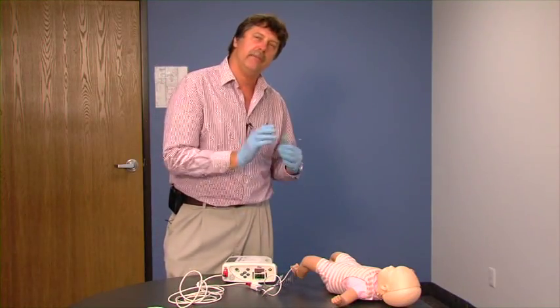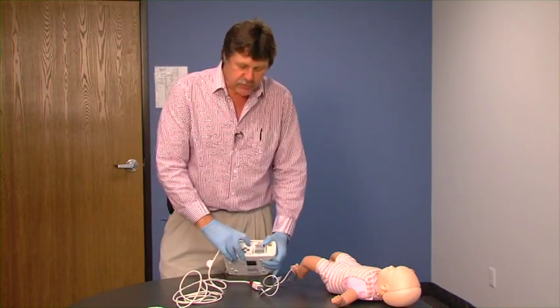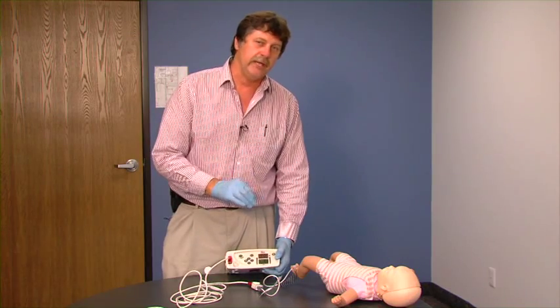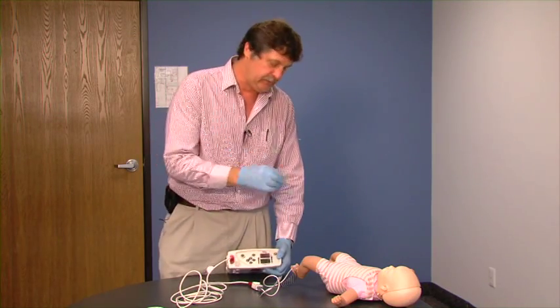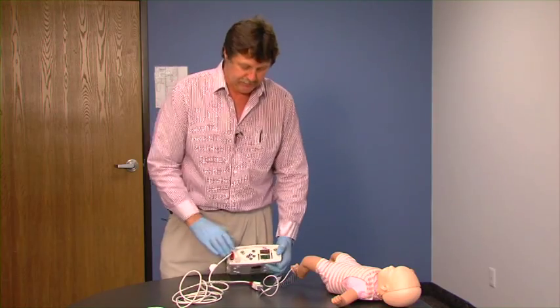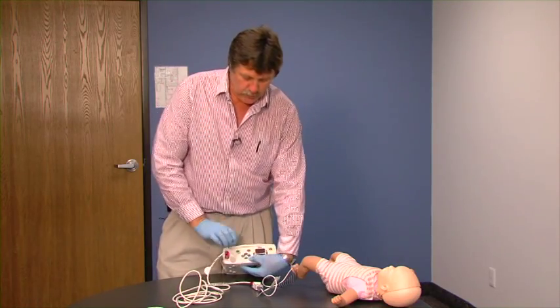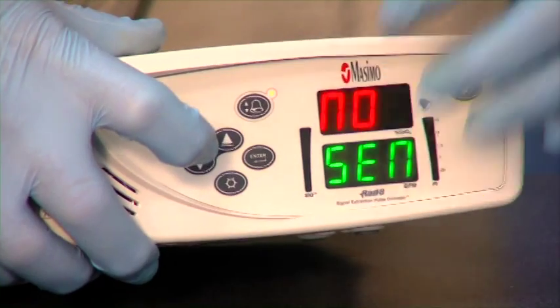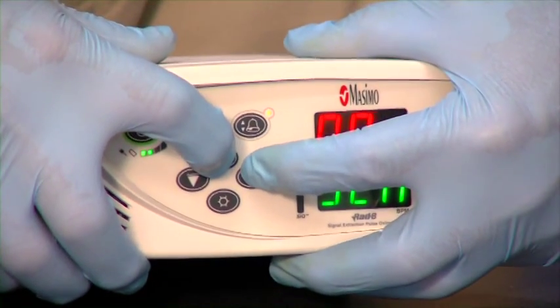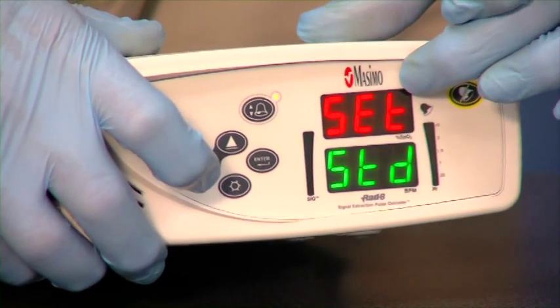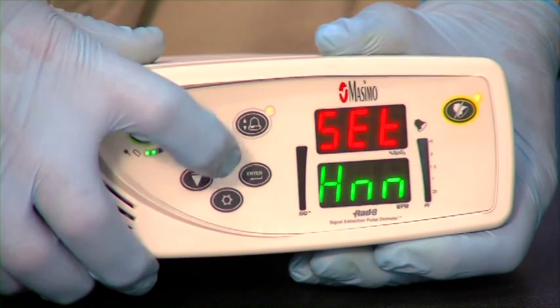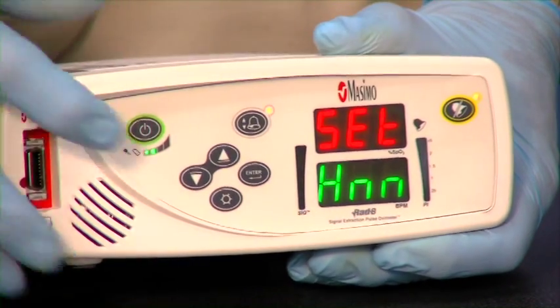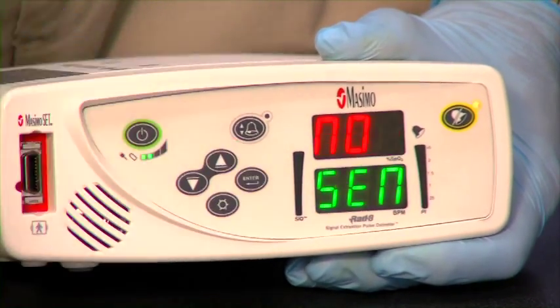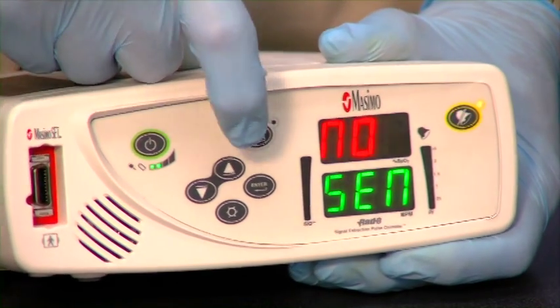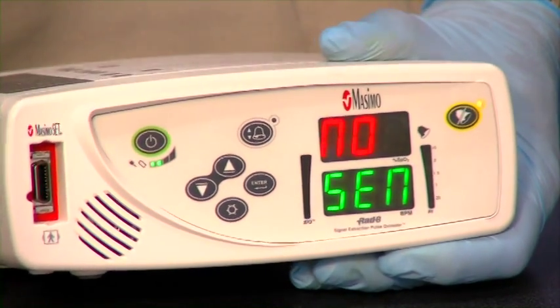Before we deliver the Masimo to the patient, we need to make sure that those parameters are locked in place so that nobody can adjust them. We want them to be set in accordance with the doctor's prescription. And in order to do that, we need to press our up arrow and enter button again at the same time and hold that down until it reads set in the upper window. We hit our up or down buttons to scroll to HNN. We press enter. Our parameters are set so they can't be changed in the home.